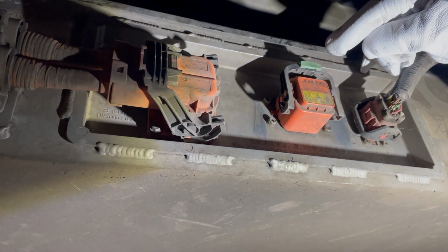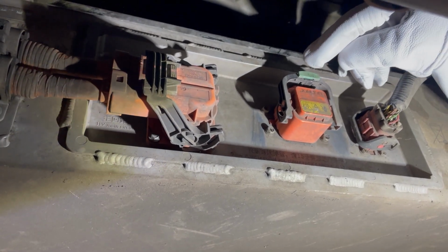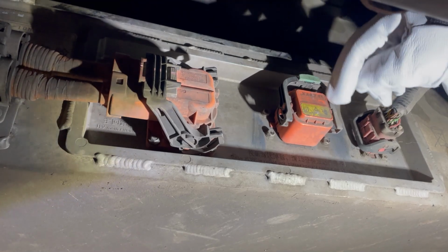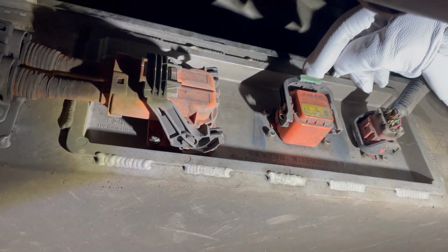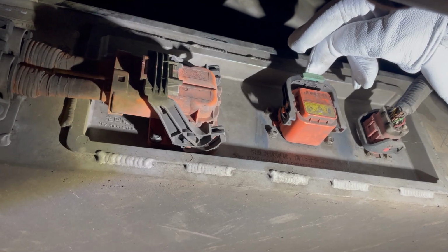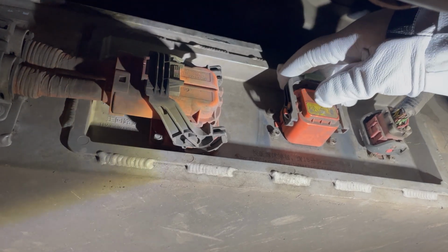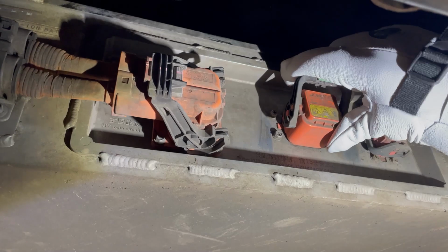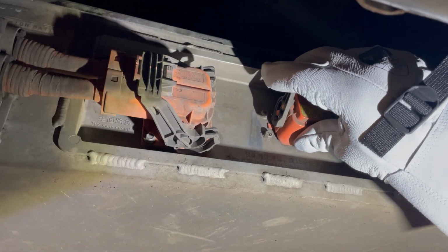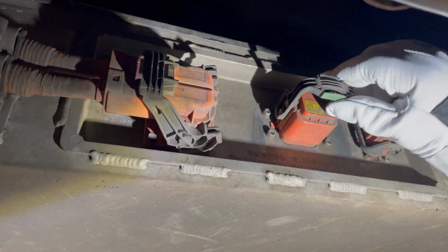So here's a manual service disconnect. All of these plugs have a secondary lock on them. They're normally a different colour to the rest of the plug, so in this case it's the green tab here. So we've pulled it out. We've got the gloves on, and essentially what you do is you pull the lever forward. It's tight, right here, and then we just unplug it.